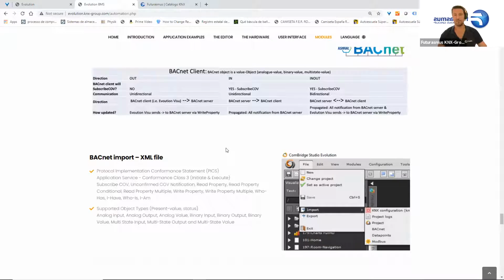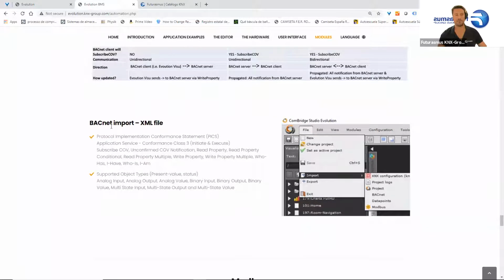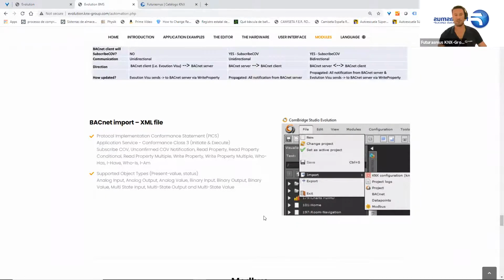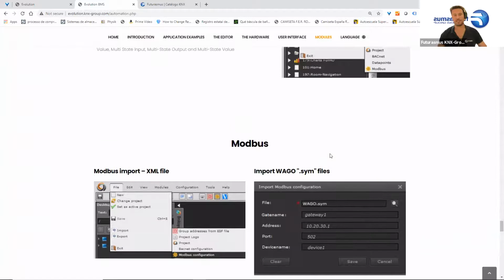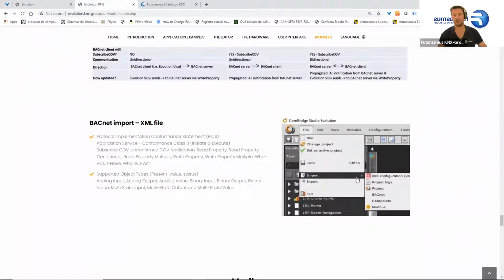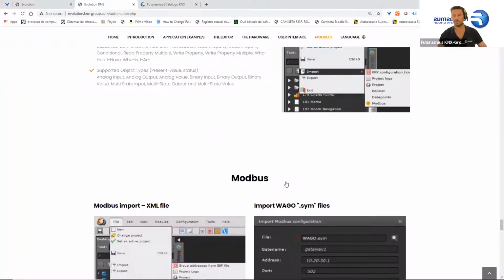The evolution will do all the management tasks, all the scheduler functionality and all the automation tasks. So you don't really need it in the other, unless you do, and then you will need to use a gateway which can support that. But you have this direct connection with BACnet, and then you can do a BACnet import with the XML file, so that you have all the process points in the evolution. There's no auto discovery implemented in the evolution yet, but there are very nice simulators and auto discovery tools which you can use in combination with it, for instance.